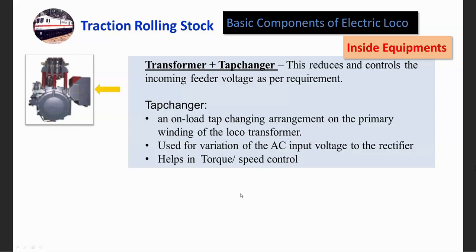The tap changer is an on-load tap changing arrangement on the primary winding of the locomotive. In electrical engineering we have two kinds of equipment: one that can be operated on load, meaning even when current is passing through it, and the other offload, where we must ensure no current is passing through before changing the position of a gear or switch. It is not possible to switch off the incoming power supply to the loco at regular intervals.